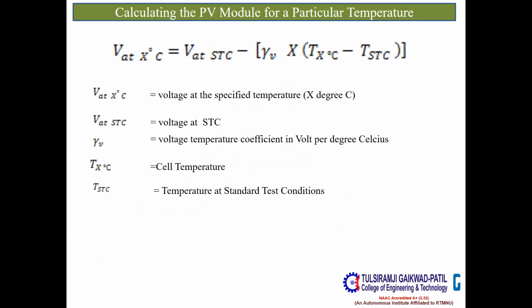Yes. So this formula is very important. All the students, you can note down this formula. I'll explain what exactly this formula will help you to know: what would be the output from a particular module at a given temperature. So V at X degree Celsius is equal to V at STC. STC means the standard test conditions for which that module is tested before it reaches the clients. Minus, in the square bracket, you will find rho V. Rho V is nothing but the temperature coefficient. This rho V would be specified by the module manufacturing companies. So whenever they test their modules in the factory and come to the parameters, they will give all this data on the data sheet at the backside of the solar PV module. From there, you can take these values. So multiplied by T at X degree Celsius minus T at STC.